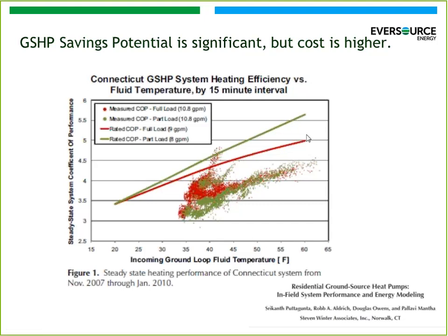But the scatter lines here were actually the measured COPs that this unit saw. In other words, an engineer went out there and was taking measurements of water flow and water temperature and power use, and was able to calculate what the actual COPs were compared to the rated. And they're lower, and they're not alarmingly lower. In fact, they're expected to be lower because these rated COPs don't fully account for some of the pumping and fan costs of the geothermal unit, whereas these measurements did fully account for the total consumption of the unit.